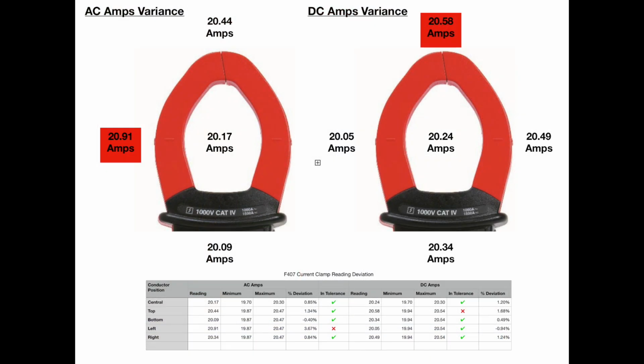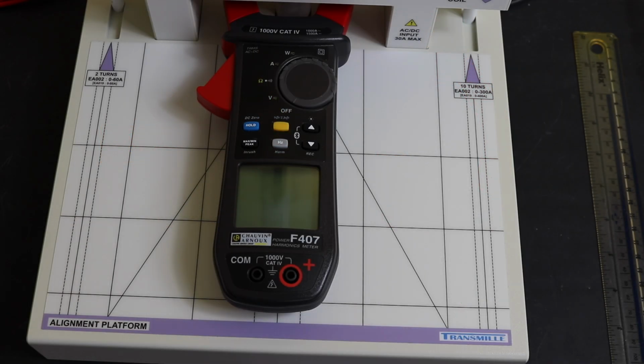Put this little table up here showing the results of the positional tests. You can see that a couple of them are just ever so slightly out, marked up in red there. They're not out by much, but it does show you that position of the conductor in the clamp can affect the reading that you are getting, so it is worth paying attention. We'll move on to the inrush measurement function here, because that's quite an interesting function.